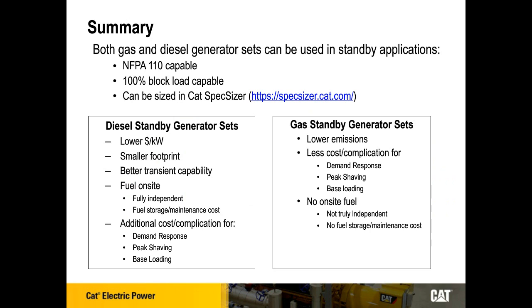Getting to the summary: both natural gas and diesel generator sets can be used in standby applications. As Bailey mentioned, they are NFPA 110 capable, and they are 100% block load capable as well. They can be sized in our CAT SpecSizer software — you can go to specsizer.cat.com, and if you don't have an account yet, you can log in for free and do your own sizings on both gas and diesel generator sets there.